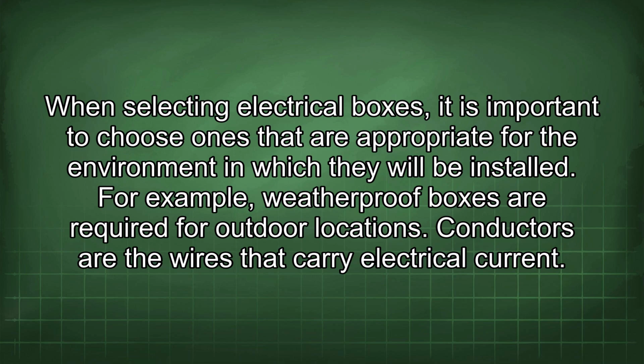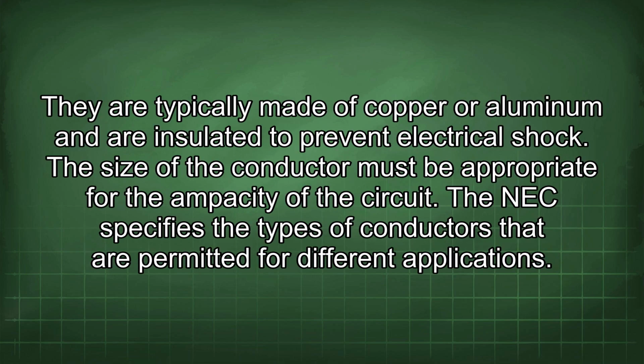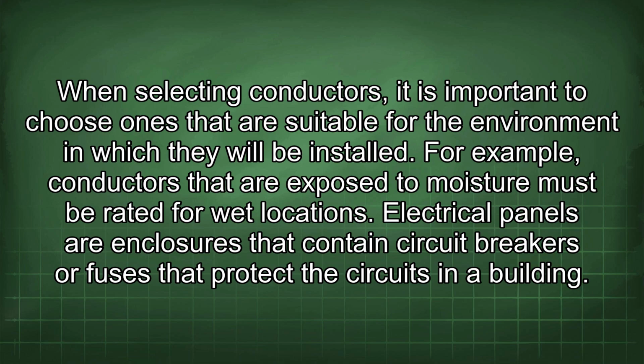Conductors are the wires that carry electrical current. They are typically made of copper or aluminum and are insulated to prevent electrical shock. The size of the conductor must be appropriate for the ampacity of the circuit. The NEC specifies the types of conductors that are permitted for different applications. When selecting conductors, it is important to choose ones that are suitable for the environment in which they will be installed. For example, conductors that are exposed to moisture must be rated for wet locations.